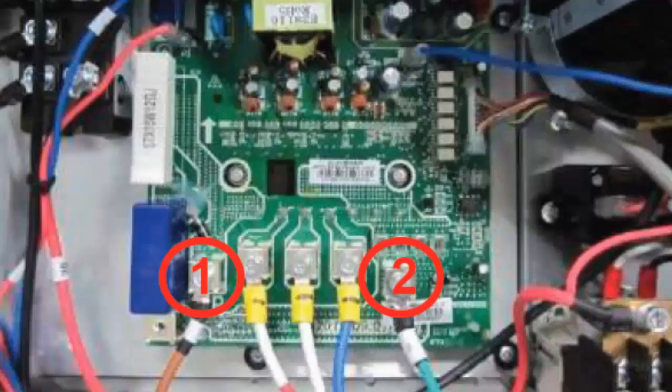6. With no power, considering that capacitors can store energy, disconnect terminals 3, 4, and 5 of the inverter compressor. Measure the resistance between any pairs of terminals from terminals 1, 2, 3, 4, and 5. All values should be infinite. If any value approaches 0, the inverter module is damaged and must be replaced.